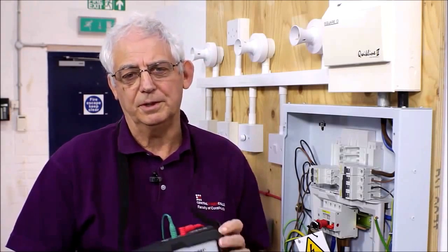The value which we must be below, as far as Guidance Note 3 tells us, is 0.05 ohms. This can create a slight problem because Guidance Note 3 also tells us that these instruments have to be accurate between 0.2 and 2 ohms. So we're measuring something that's very, very low. Some of these instruments really aren't that accurate. This one's okay, but not all of them are.